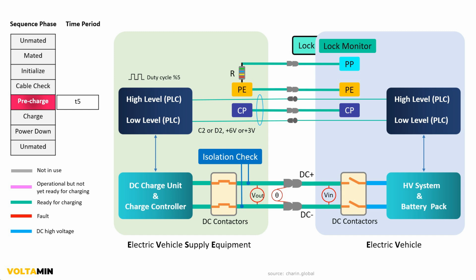The requested DC current is limited to less than 2 A to prevent inrush current during the voltage alignment process. The EVSE responds by gradually increasing its output voltage, VOUT, to align with the EV's internal voltage, VIN. This step ensures that the voltage levels are synchronized before high current charging begins, protecting both the EV battery and the charging station components.